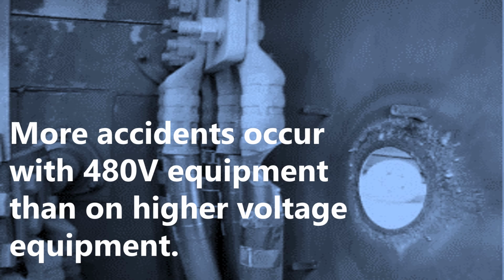Now, more accidents occur in 480 volt equipment than on higher voltage, and I hear people tell me, well, it's only low voltage, it doesn't matter. But really, the higher voltage has much lower available fault currents and much faster clearing times, so the actual incident energies are not as high as what we see in 480 volt equipment sometimes. So again, be very careful if we are saying, oh, it's only low voltage, we're okay. You're not, you're never okay.